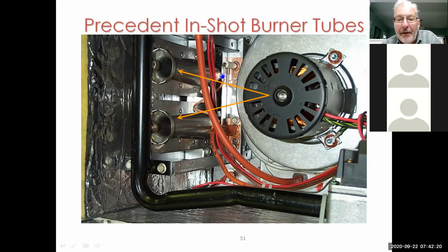Flame sensor depends on a ground, through the flame to the burner. So if you're having flame fail or flame sense issues, a few things you want to look for, of course, is make sure that this porcelain's not cracked or dirty. If you want to check the flame signal, what you have to do is pull the wire off here, put your microamp meter in series with this, and we're looking for about 2 to 4 microamps. And if you don't have that, what you want to look for, of course, is a rusty burner. Flame or the current can't pass through rust, so it has to have a clean burner.